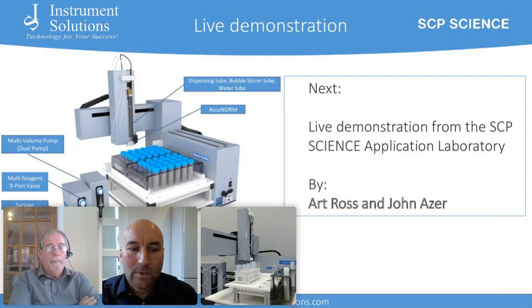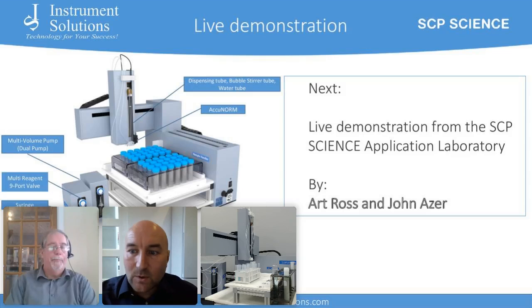Okay, so I have two other questions. The first one is from Regis Nkenda. His question is, what is the exact utility of the bulking pump? Well, the syringe pump is very precise, but it's relatively slow. So when you do a normalization, you use the bulking pump to first add the biggest part of the volume. The bulking pump is less precise, but it's fast. And then with the syringe pump, you add the last bit to have the good precision for the normalization.